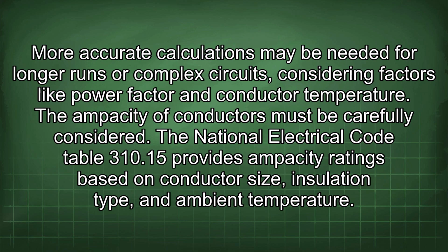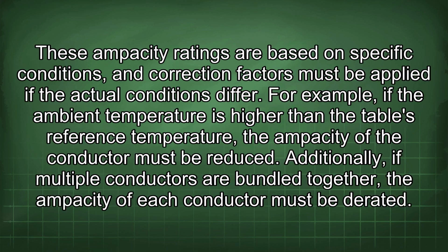The National Electrical Code Table 310.15 provides ampacity ratings based on conductor size, insulation type, and ambient temperature. These ampacity ratings are based on specific conditions, and correction factors must be applied if the actual conditions differ. For example, if the ambient temperature is higher than the table's reference temperature, the ampacity of the conductor must be reduced. Additionally, if multiple conductors are bundled together, the ampacity of each conductor must be derated.